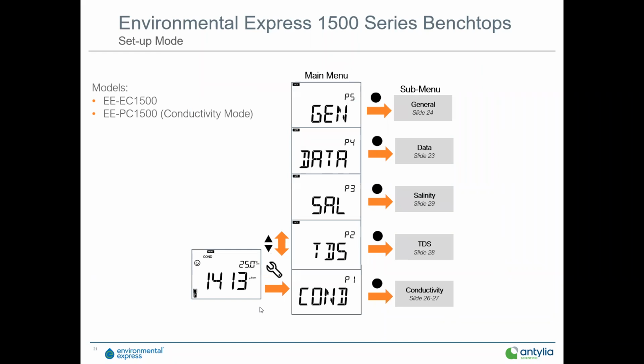So this gives a quick look at, from your measurement screen in conductivity, you can drill into the conductivity and net subprograms, go up to TDS, go up to salinity, go up to data, go up to general. The key here is parameters or measurement mode, data, and general. Those are the three main paths into the program of this instrument.